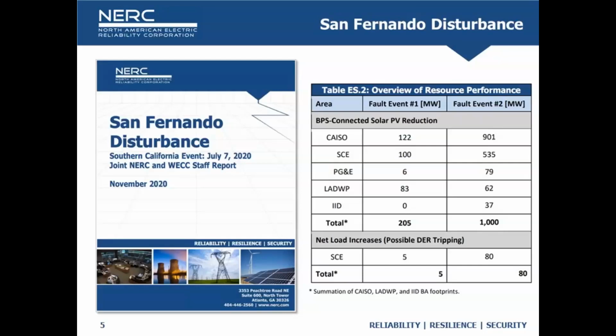So a very rare situation, but we did get a bolted three phase fault for all intents and purposes in the Southern California area. As planners, we study bolted three phase faults and we don't see them that often in the real world. Now we can at least have an event we can point to with a disturbance report that says, well, we do have bolted three phase faults and they have a decent impact on the grid.